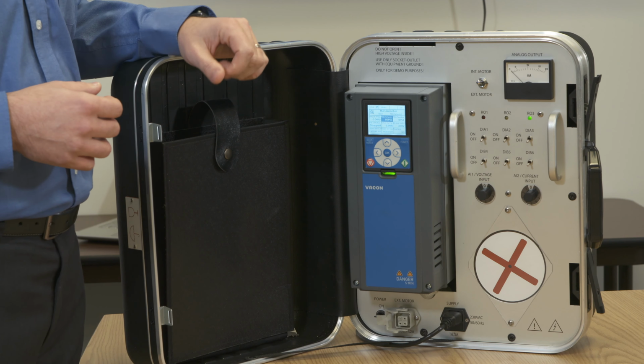Currently, we have output frequency of 0. The drive is not running. We have an 80 psi set point that we want to maintain pressure at 80 psi. The PID feedback is 0 psi, but we can change that with the analog input too. You'll see that shortly. The status of the PID control is stopped. This will tell us if we're soft filling pipes at the beginning. It will tell us if the drive is sleeping. You'll see that shortly. Motor current, this is a very small motor, so the current will be fractional.